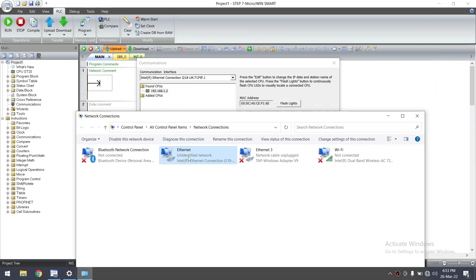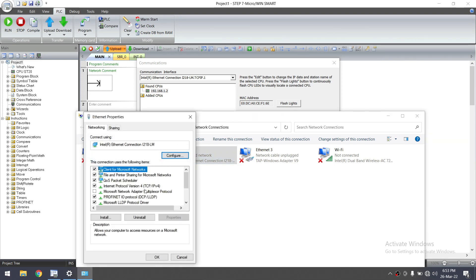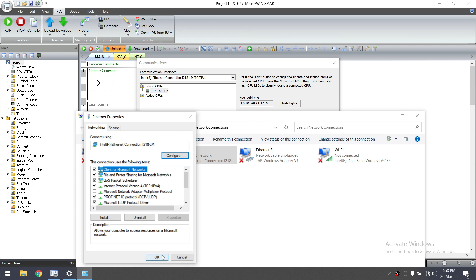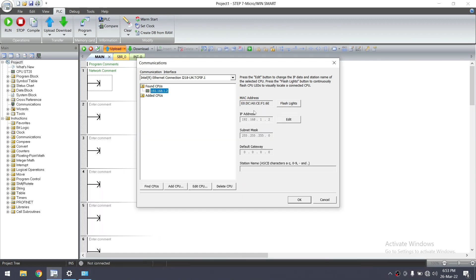The PC IP address should be in the same series as the PLC. Go to Properties and set it to 192.168.1.80 — something different from the PLC address. The PLC address and PC address should not be the same. Click OK.